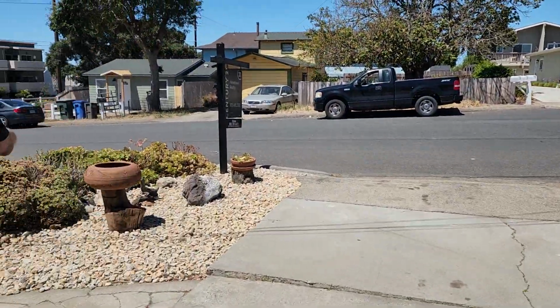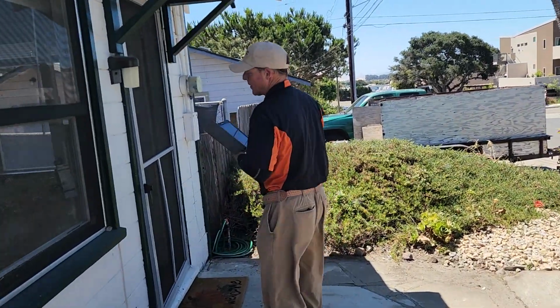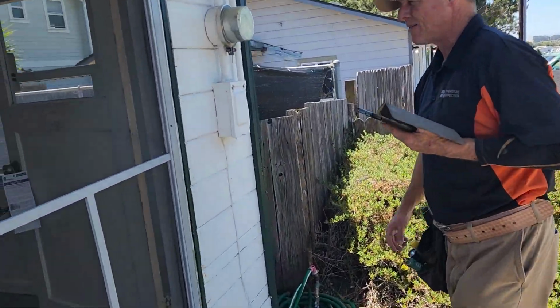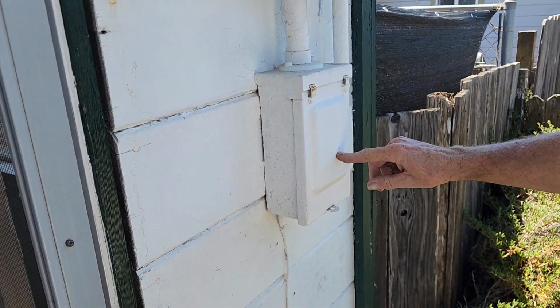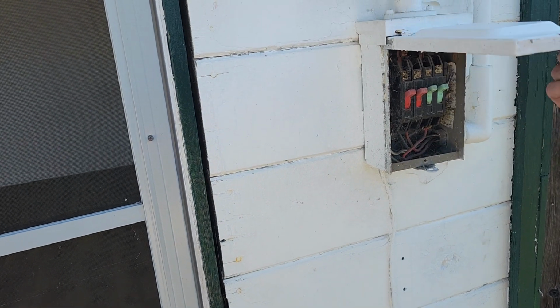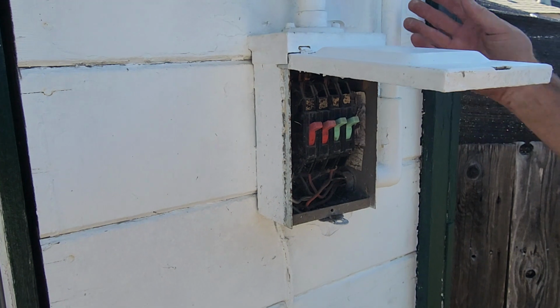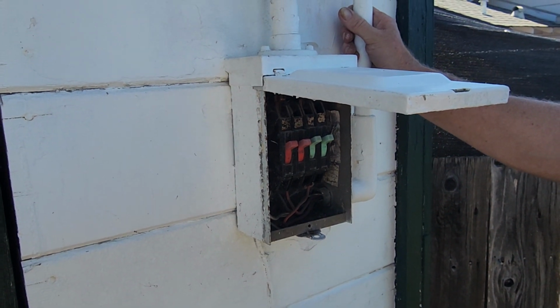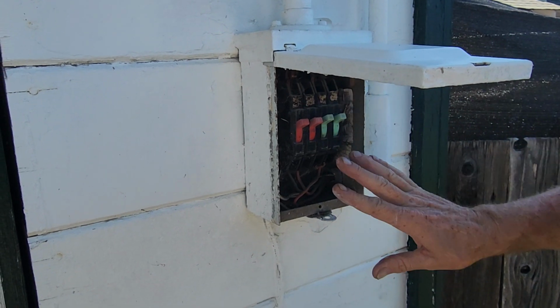Right, and this is kind of expected, I guess. 1951. The original wiring was a 2-wire system, so you have open ground throughout the house. Okay. It's made by a company called Zinsco, which were alleged to make defective breakers and parts. But it's been here for 70 years with Zinsco and been fine. So we just recommend it be evaluated. We don't recommend replacement.